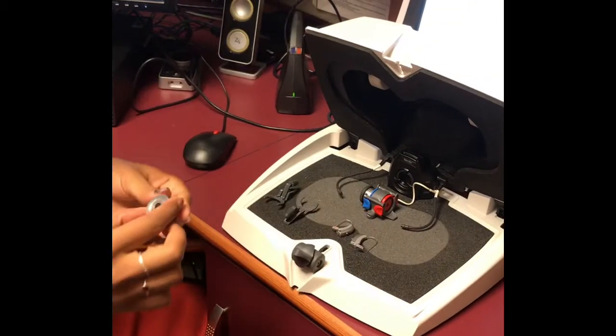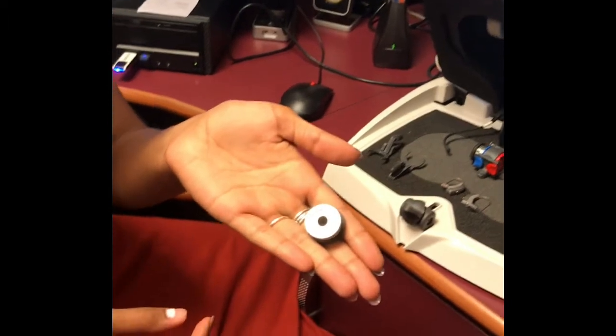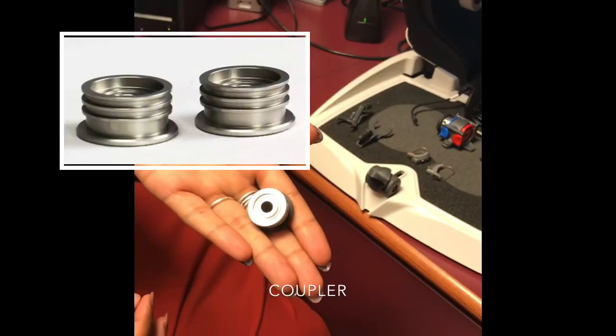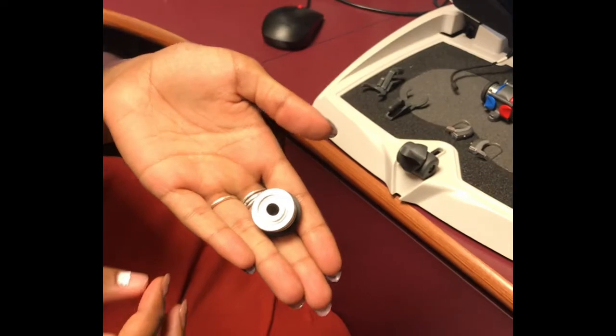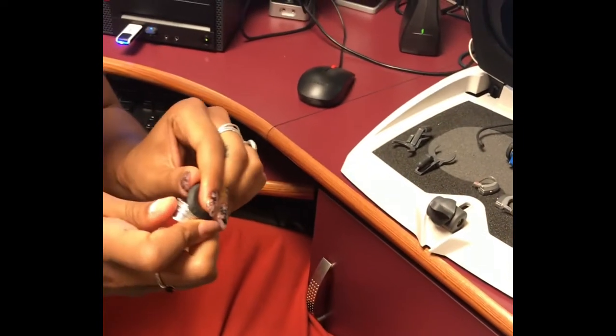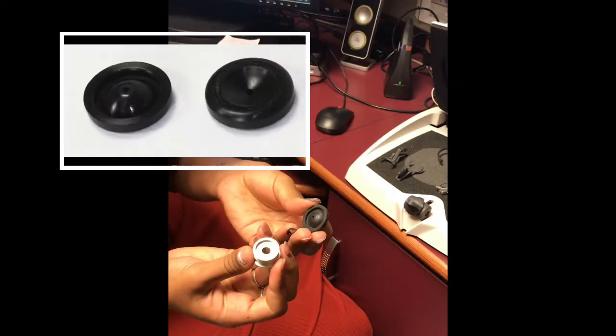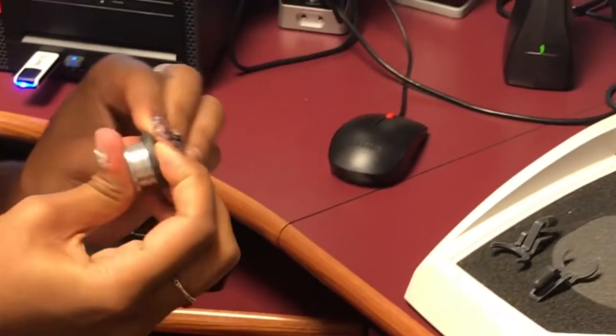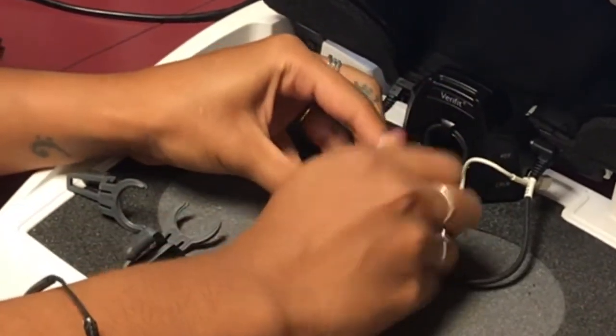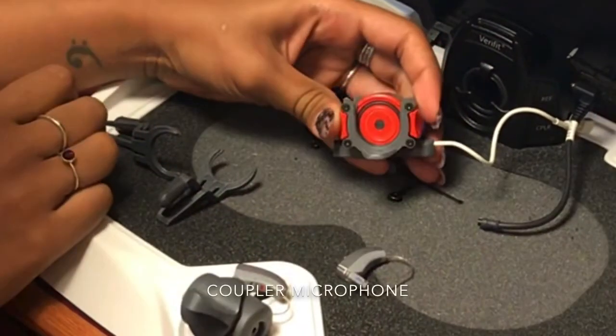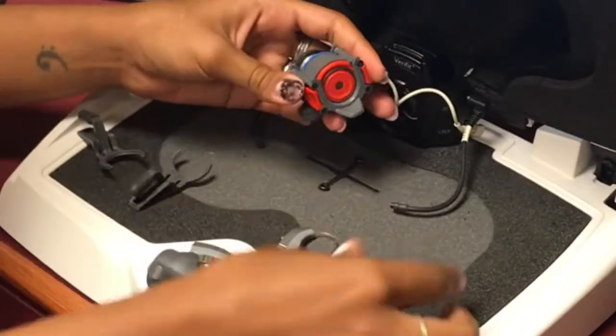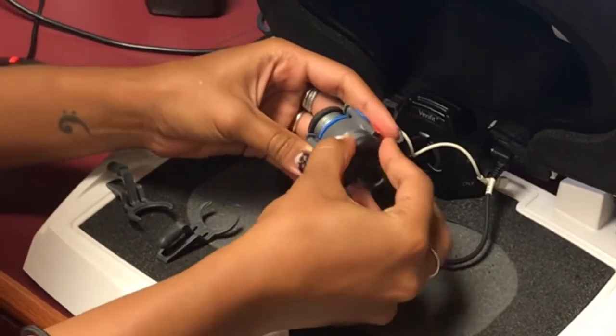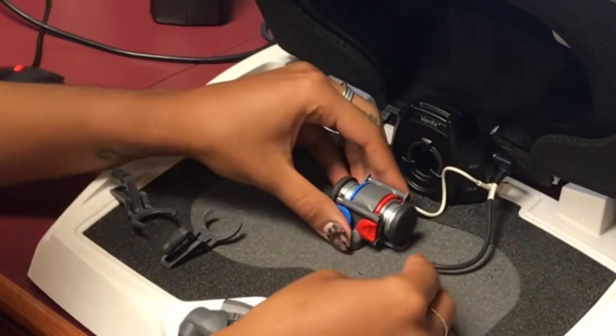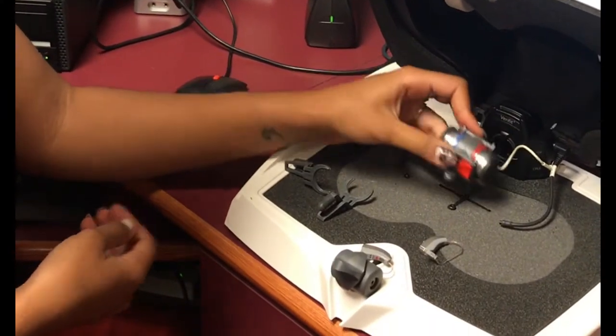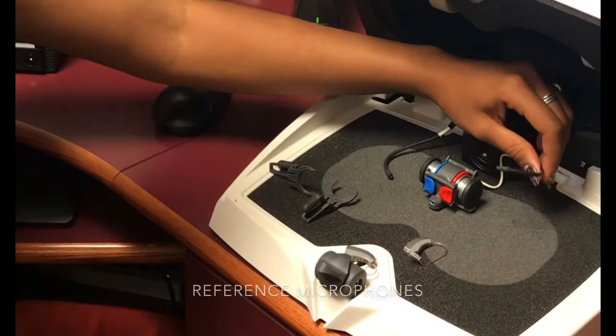What I am holding is the coupler, which is where the receiver of the hearing aid sits in. This coupler is used for different types of hearing aids, but today we will look at the RIC. For the RIC to fit seamlessly inside the coupler, we have this black rubber adapter, and I'll show you how that fits inside later. The small black hole you see here is the coupler microphone. The coupler slides flush against the microphone like so. And on either side of the couplers, we have a reference microphone.